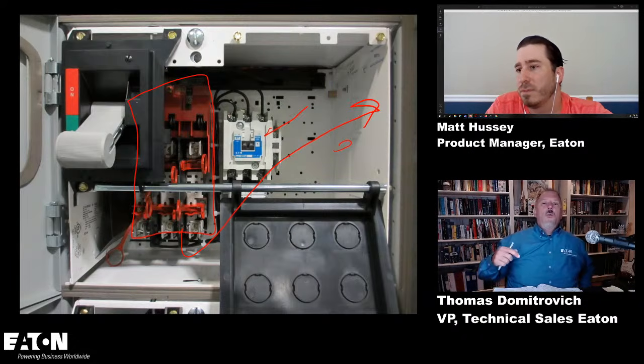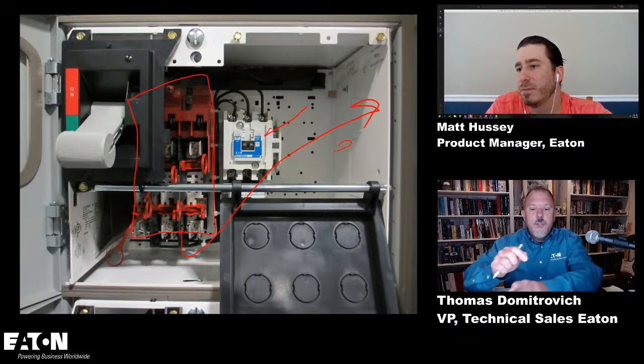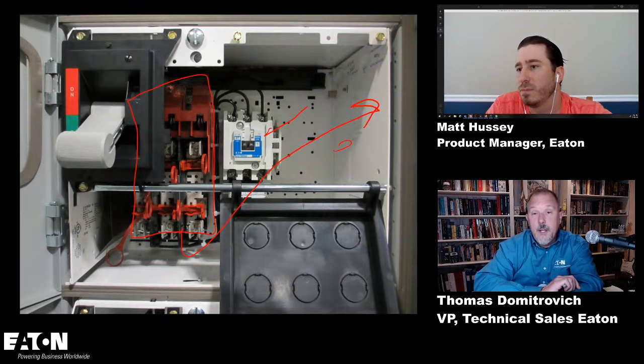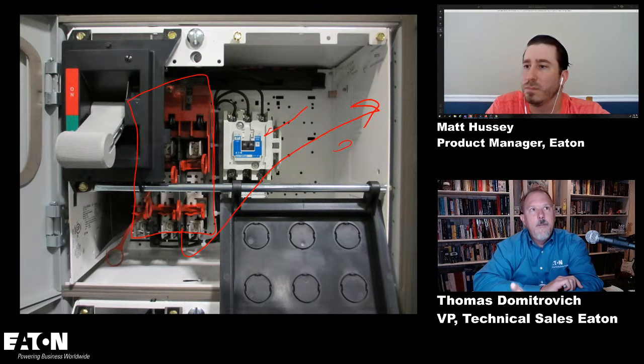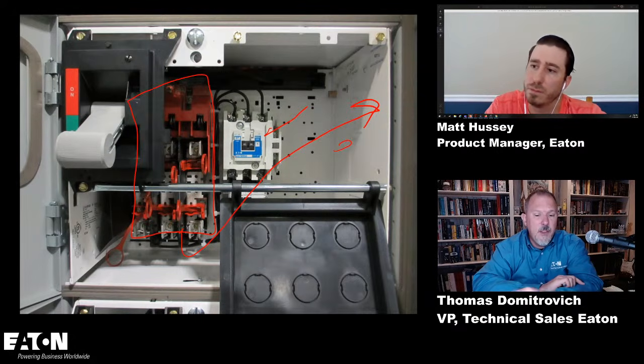The fuses that they put in there are going to be listed fuses, because that's what we use to protect motors. The switch itself would not. It's just disconnecting, so there's nothing protective as part of the switch. If it was a fusible MCC with the fuses in there, you wouldn't have the same concerns as you would with an HMCP, because the HMCP is instantaneous only. But there might be other issues.